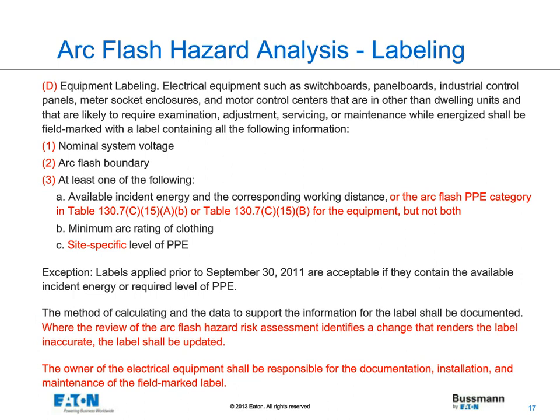As another alternate, you can mark the minimum arc rating of clothing, or for some conditions, you can mark a site-specific level of PPE. That means something only to that specific employer. So there might be an industrial facility that does their analysis and decides they have perhaps a two-level category, level 1 and level 2, and that means nothing to anyone except that facility and that owner.